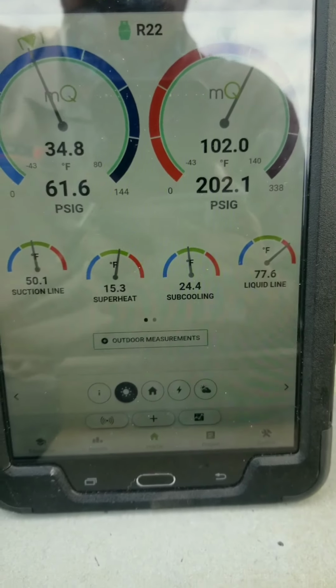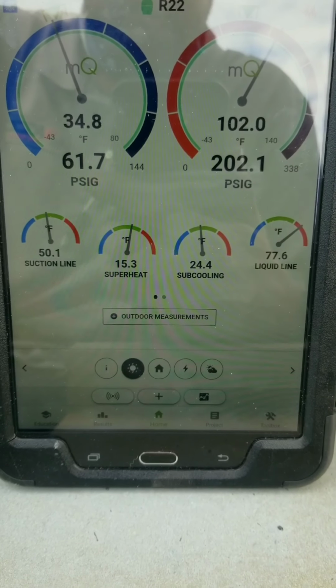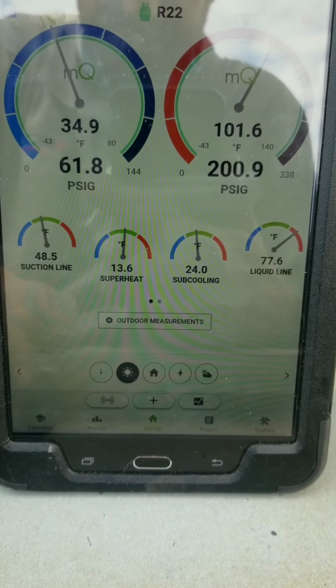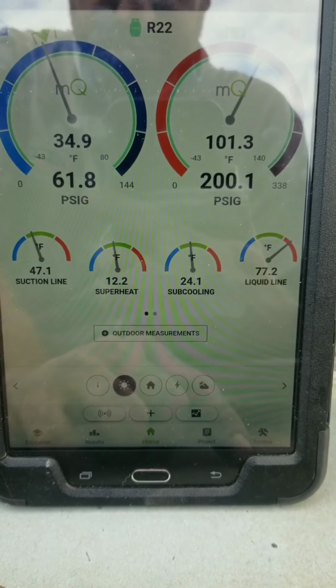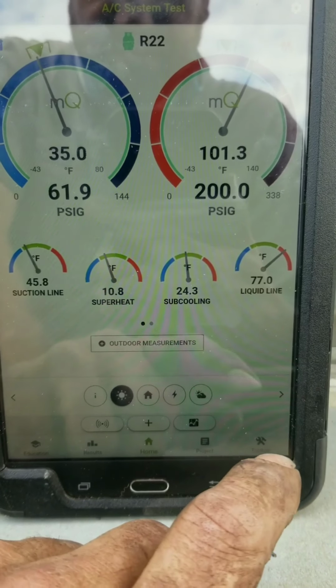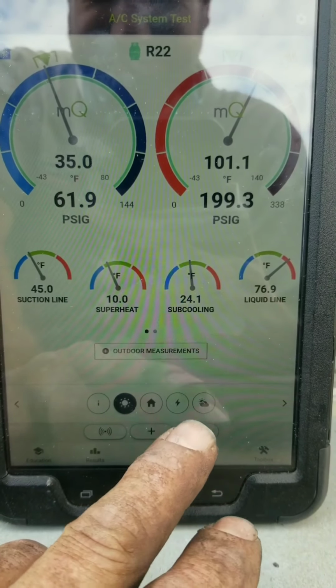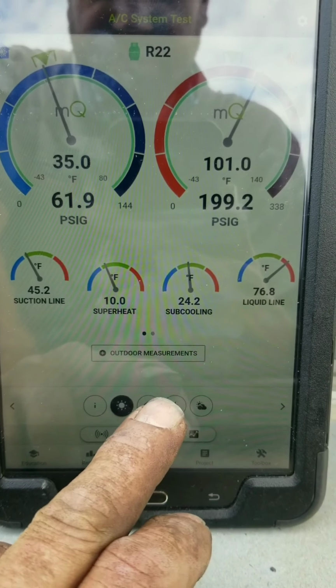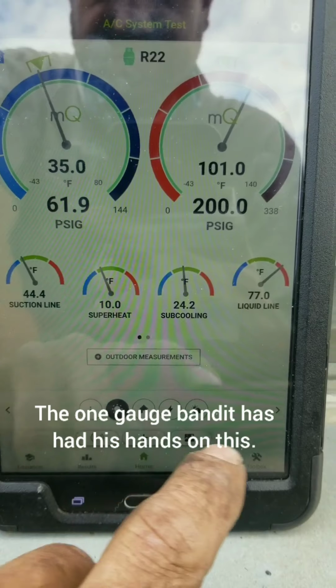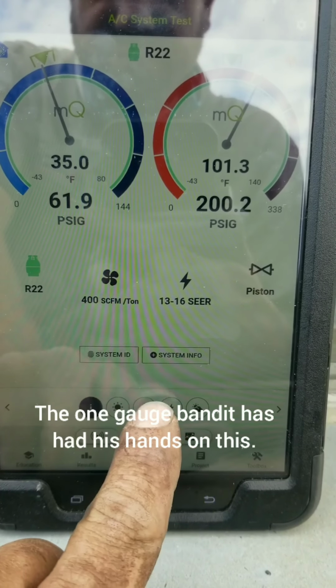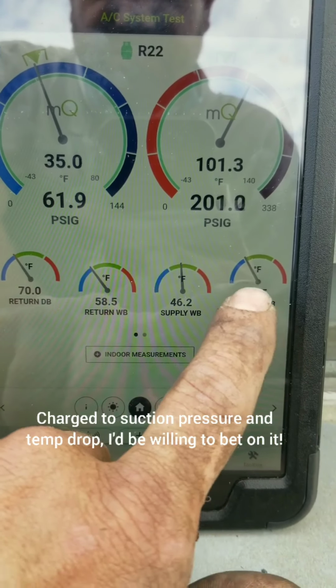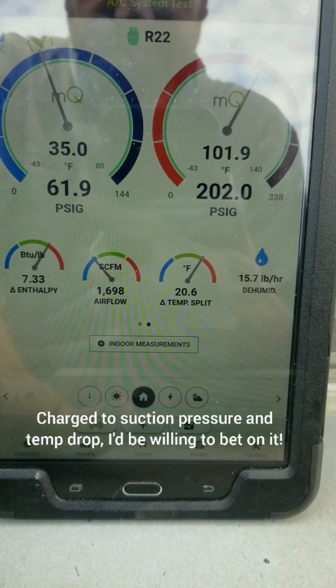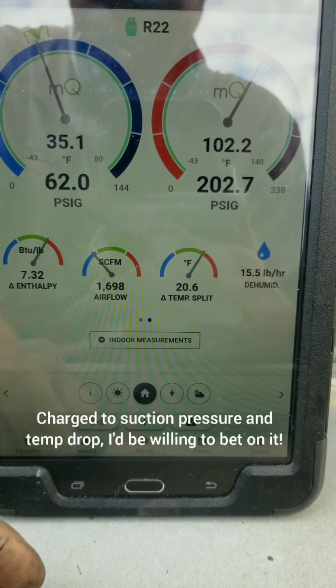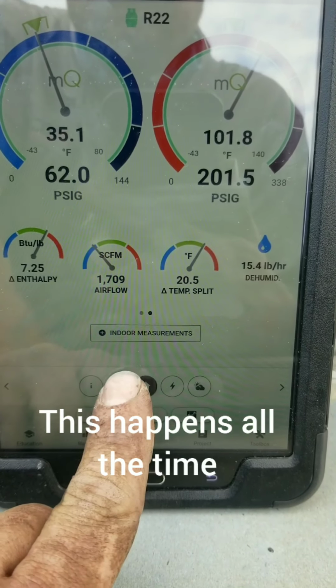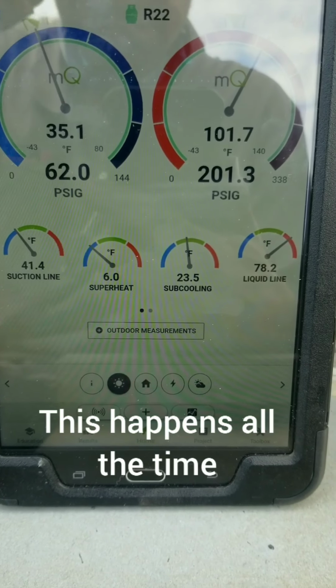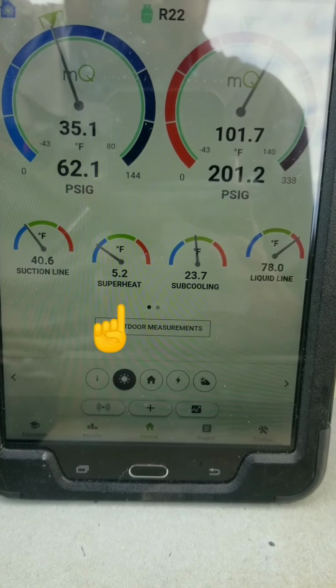So we've been running for a few minutes here. It doesn't look great. It's not going to be perfect. This thing's 15 years old. It's seen better days, but subcooling's kind of high. I'm actually reading discharge pressure, so you know, we're really going to monitor our superheat, which 10 degrees I can deal with. We're running 20 degree temp drop, 20.6, so that's pretty good. I'm sure we have some airflow issues.